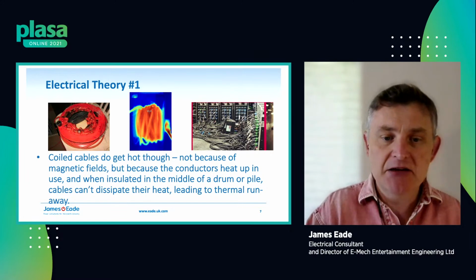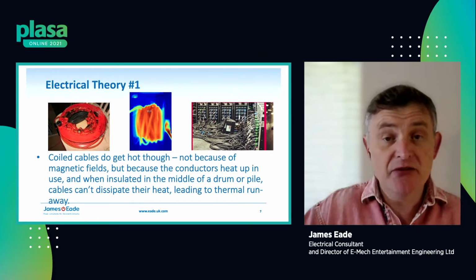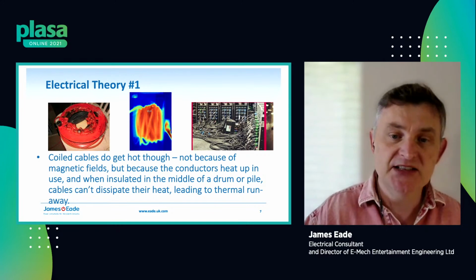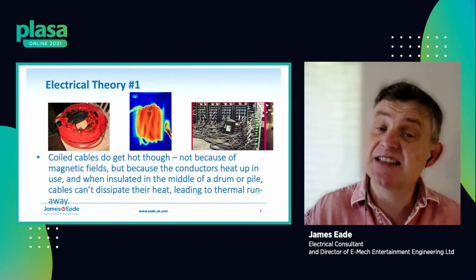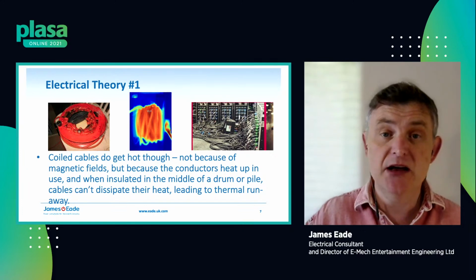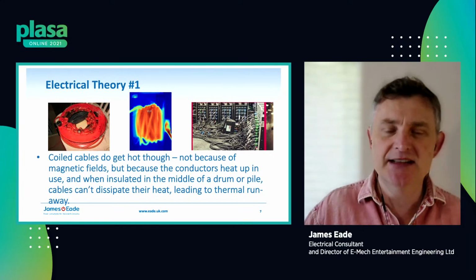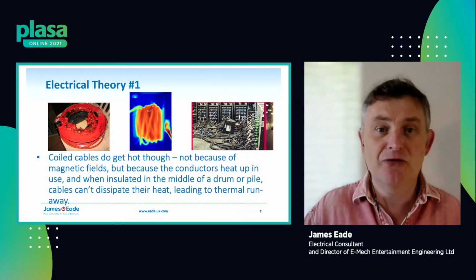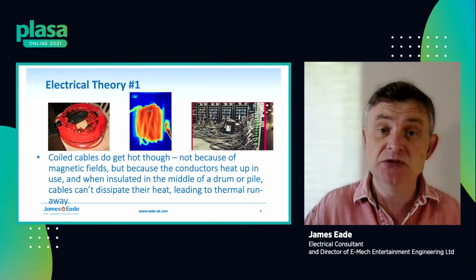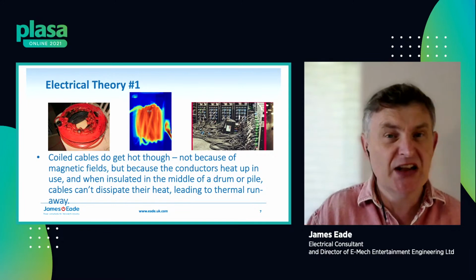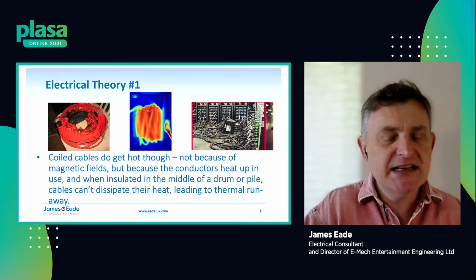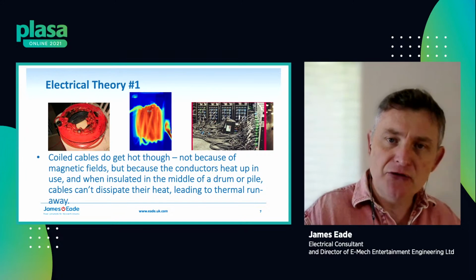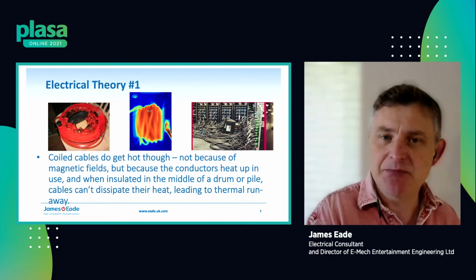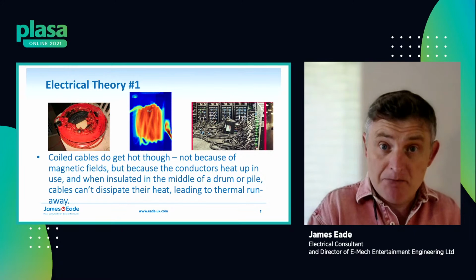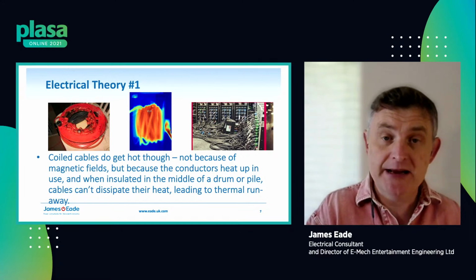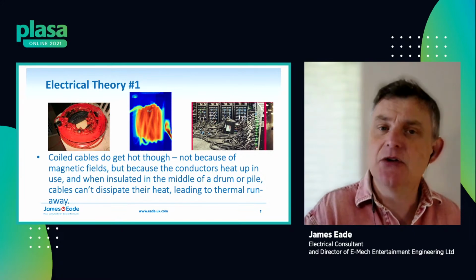A good example is a pile of cable on a fly floor, or dimmer city, or a cable coiled up on a drum with a load on it. You can demonstrate this at home: plug a kettle or fan heater into a coiled up cable, and after 5 minutes, unwind it and the center will be really hot. That's because the current flowing through the resistance dissipates power, and in the center of the drum, covered by more cable, it can't dissipate that heat, so it gets hot.